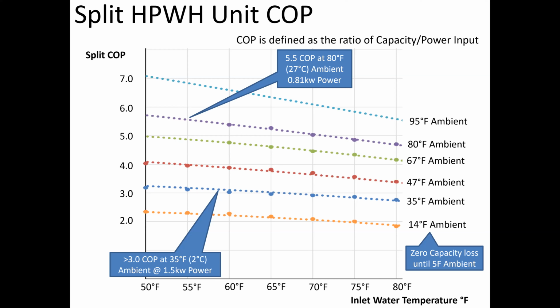The cooler it is, the different the COP level, or coefficient of performance, is going to be on these particular systems. With these ones, obviously it works a little bit backwards in that the warmer the ambient temperature, say today it's 80 degrees outside, the COP suddenly shoots up because there's a little bit more heat to steal from the outside, so what we see is a COP of 4.5, which means the unit draws around about 800 watts per hour.